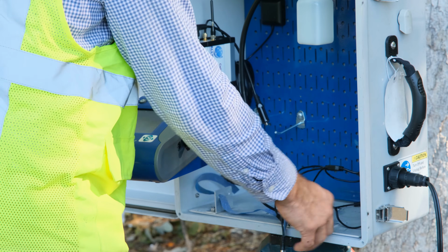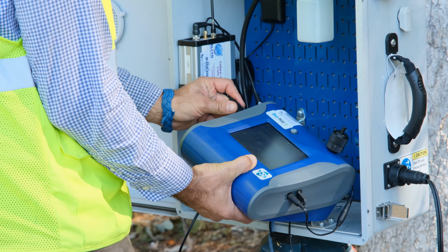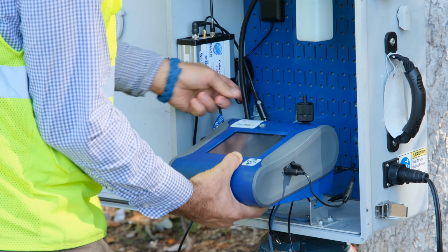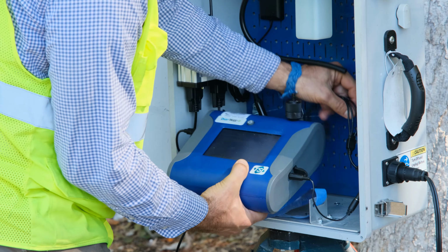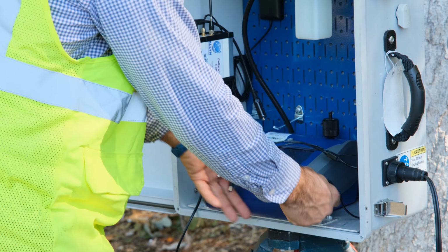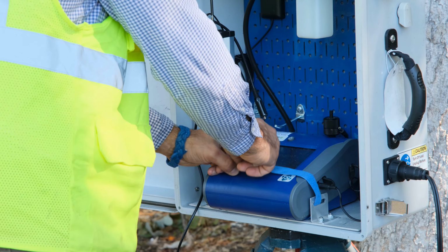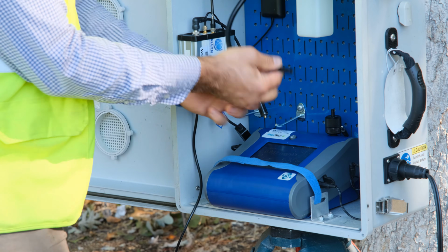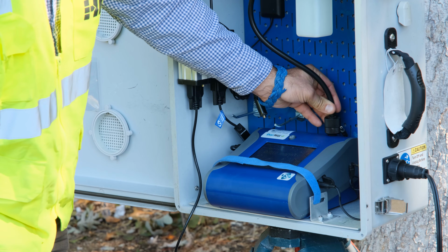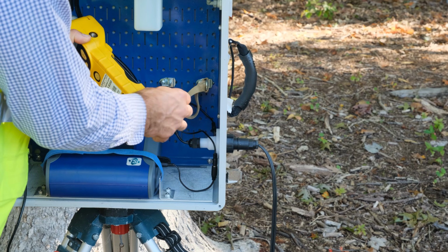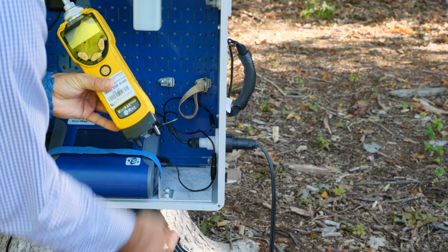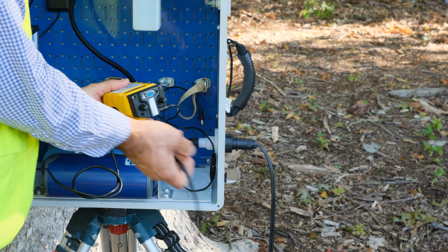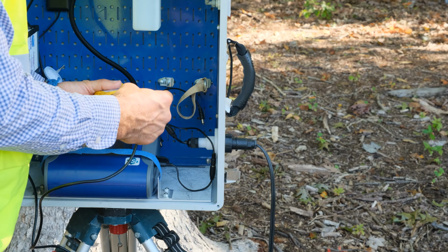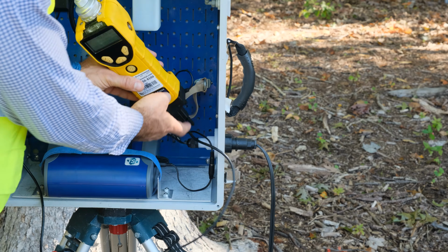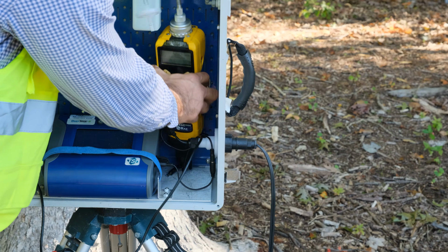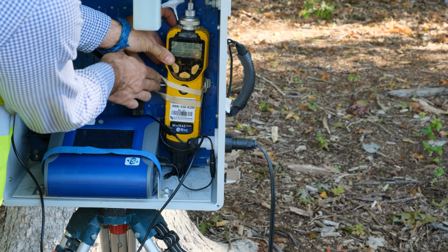Once you're done calibrating, you want that dust monitor to go back in first. Make sure you've got your power plugged in as well as your USB for the EnviroCore. Hose goes back onto the Micron filter. Going to reinstall the PID and make sure that power is attached to it. Comms cable goes to the bottom of the PID. Make sure that data is being received by the EnviroCore.